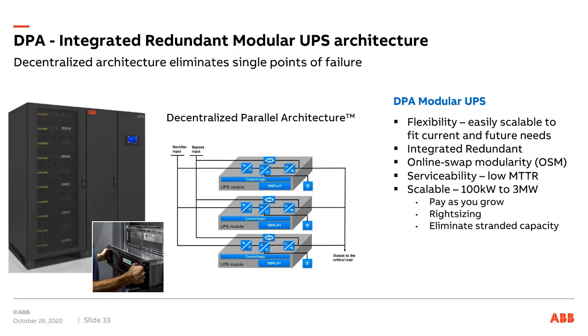I think most vendors offer modular and monolithic type UPSs, but I believe the ABB one is the only one currently with a decentralized design, with a full N+1, or technically also N+2, whatever is required, redundancy in one frame. The UPS cabinet, for lack of a better word, is just a dumb metal cabinet. There are plugs where you plug in the power modules, connected with bus bar and cable, and there are terminals to land the input, output and battery cable. But there are no active components in the frame. That's all figured out between the power modules, in this case 5, but the illustration shows 3.